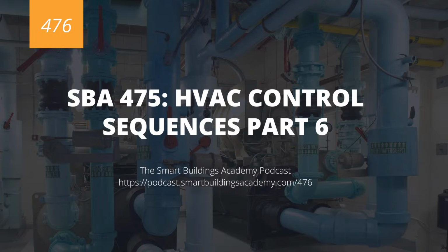All right, so the chilled water leaving temperature of 55 degrees, adjustable. Then there's some pressure control because this is a constant volume pump, and it talks about the chilled water two-way valve bypass located across the chilled water supply and return lines at the end of the main, and it's essentially acting as a way of balancing the pressure in the piping since we're using constant volume piping. So that's something you'll see sometimes, and it's something we'll cover in a future episode when we talk about pumping, piping, decouplers, bypass valves, mixing valves, etc. But there you have it, folks, right?